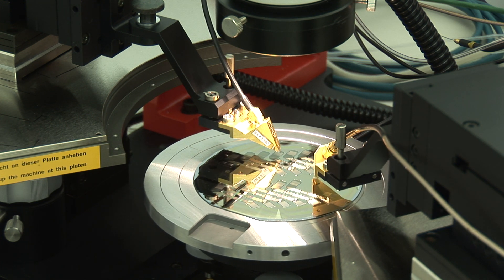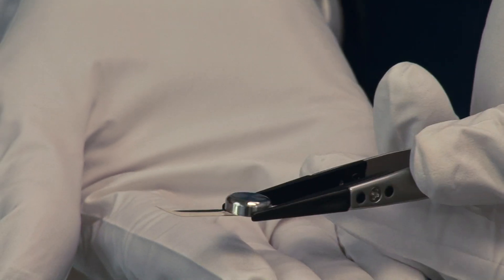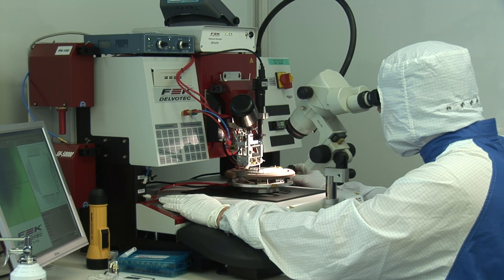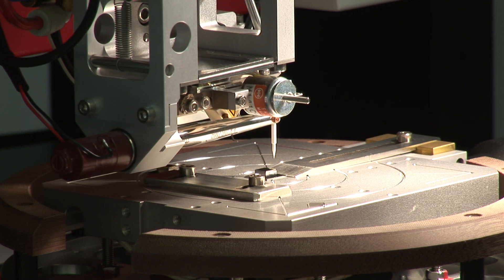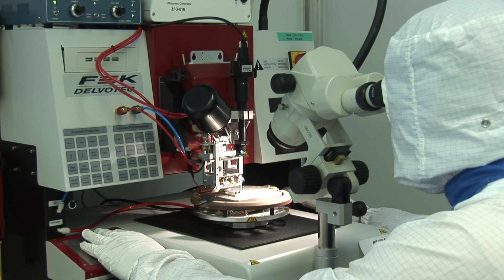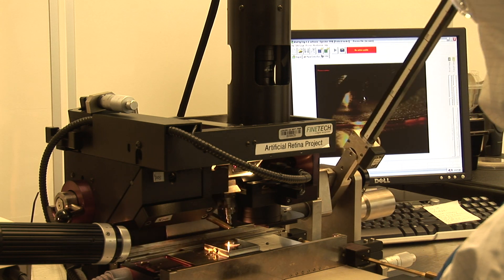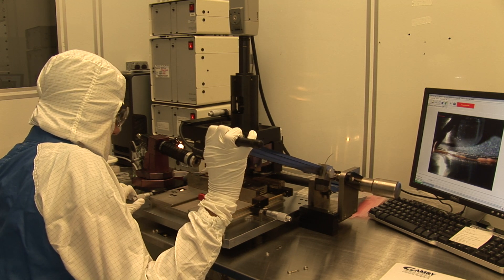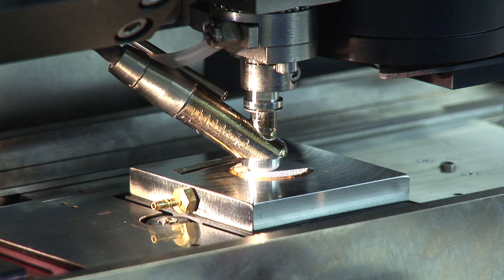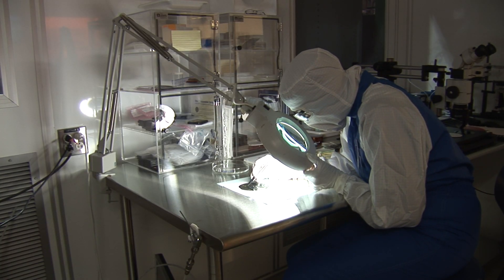The array by itself is just one part of the assembly that will eventually be implanted into the patient. There also needs to be a package of miniaturized electronics, only about the size of a hearing aid battery. The device's two sets of integrated circuits are connected to one another in a machine that functions much like a sewing machine — it meticulously attaches a thin gold wire from one set of electronics to the other. It takes the machine only about five minutes to complete just over 100 separate connections, using a wire only about one quarter of the thickness of a human hair. Next, the completed electronics package is assembled onto a thin film array. Sensitive cameras align both components, which are carefully brought together and bonded using a unique glue. Using pressure and heat, the curing process takes about five minutes, and at this point the implantable device is complete.